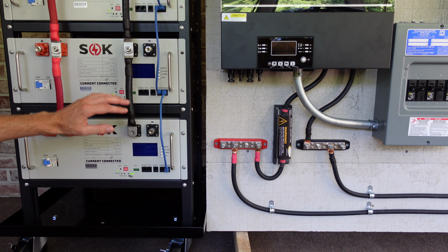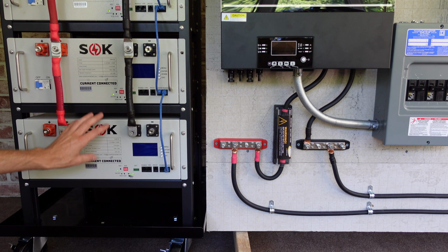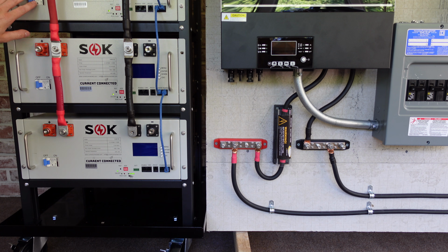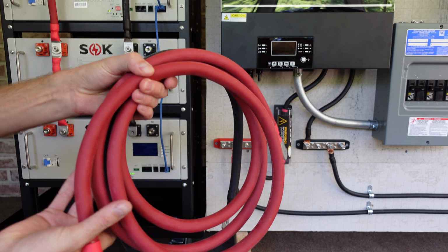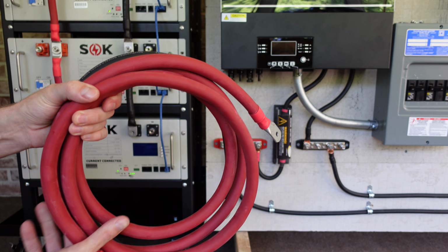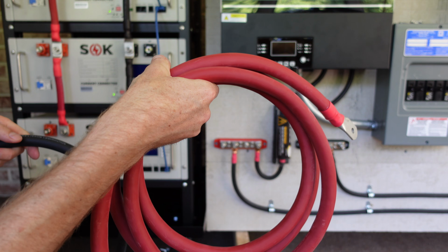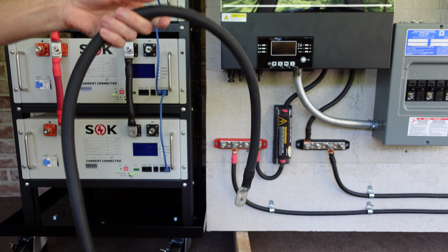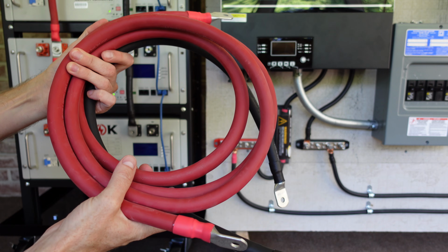So the last step in the wiring connections is to connect our batteries to our two inverter supply bus bars. So I've made sure that all of these circuit breakers are turned off on all four of these SOK batteries. They are all shut down. Going to be using some 4/0 cable for this connection. I've got a lengthy piece of red and I've got a shorter piece of black. No, these do not need to be the same length.